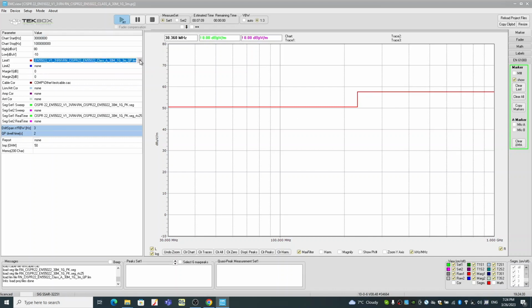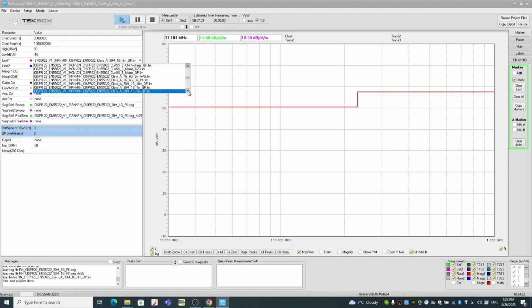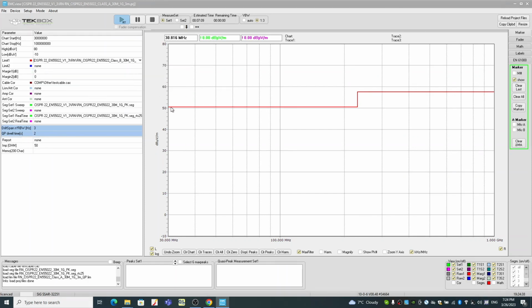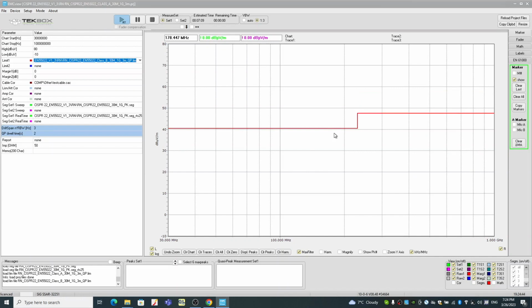If you want to have class B rather than class A, simply go to class B, and you can see here that's class B. We know class B is a little bit more stringent than class A. So if I select that, you can see the limit line drops for the test.